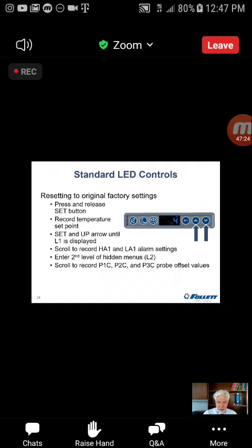Then you hit the arrows to scroll to P3C, all right? And again, hit set. It will show you the offset value on the bottle probe, all right? And the same thing, if it's not 0, record the value. Only time we have to worry about P2C is on a freezer. And if we are on a freezer, we should do that as well. So we now have all of the offsets recorded.